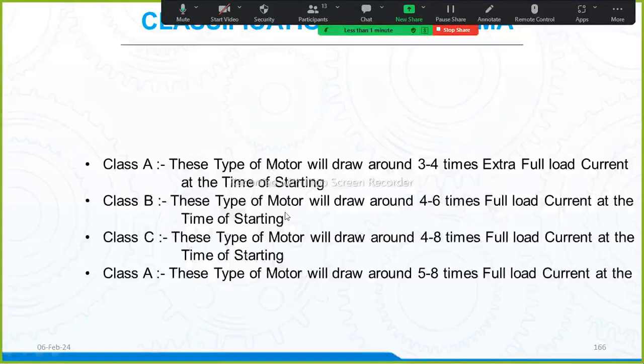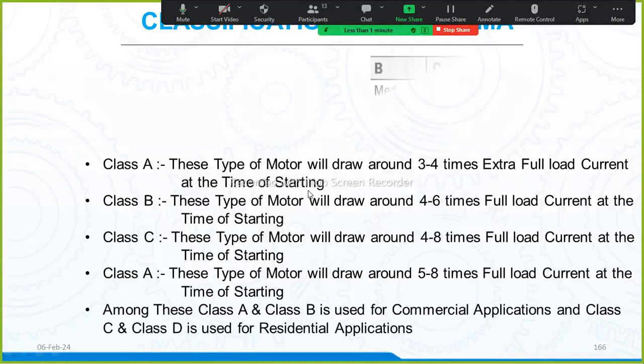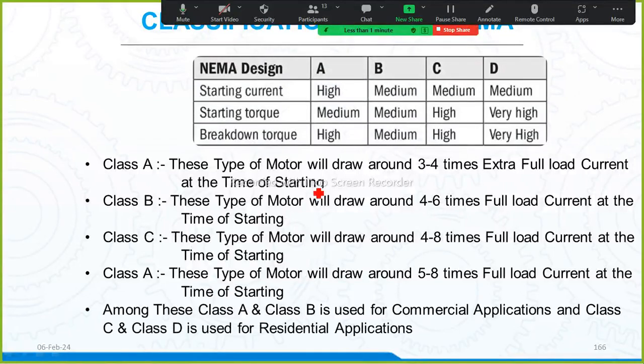Okay. Now, when it comes to here, I want to tell you one point. What is that I told you? That motor will take high power at the time of starting. So, who had given that certain standard that this much high power is taken? There is an organization called NEMA, the National Electrical Manufacturers Association, which has stated the starting current, the high current taken by the motor. So NEMA has classified the motor into 4 types: A, B, C, D. Class A, Class B, Class C, Class D.